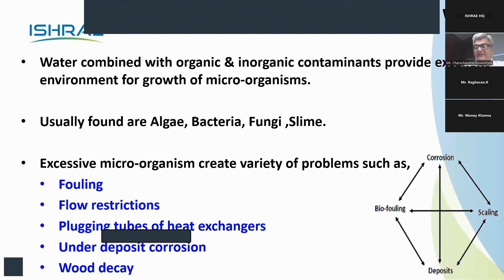Now, this dilemma you must be facing, so I thought I'll add it. See, this is a weighing scale. On one side of the pan is scaling and the other is corrosion. If I want to reduce corrosion, the scaling tendency will go up. If I'm reducing scaling, then the corrosive tendency will go up. So whenever designing the process or treatment, I have to balance it together, so scaling will not take place while corrosion is under control. This way my system will give better and longer life service in the coming years.